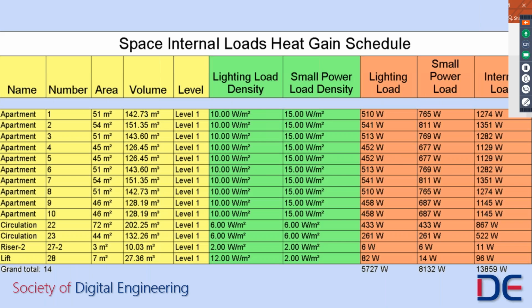And here in a separate schedule, where I've listed out all of the spaces, we can see the yellow areas. We have the area values. We have our lighting load density, and notice that they are consistent amongst the same space types. We have small power load density, and we've multiplied the densities by the area to give us a lighting load and small power load. We can add those two together to give us a full internal cooling load for that space. And also at the bottom, we can summate them, so we can look at our overall lighting load, our overall small power load, and our total internal load.